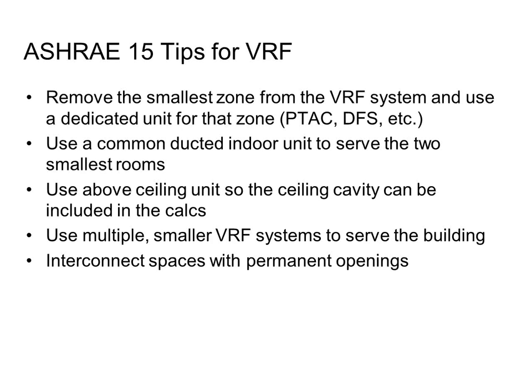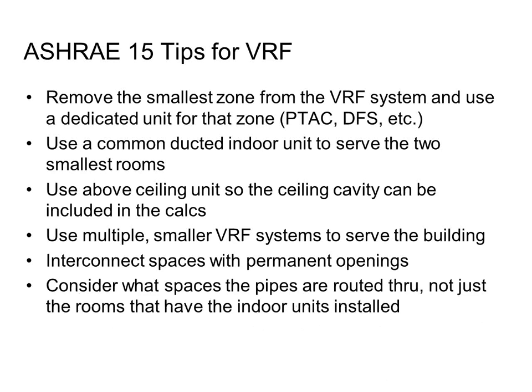A permanent opening would be literally removing the wall so they're physically connected into one zone, putting in transfer grills, putting in jumper ducts, those sorts of things that are not likely to be removed. Shaving a door probably wouldn't count.